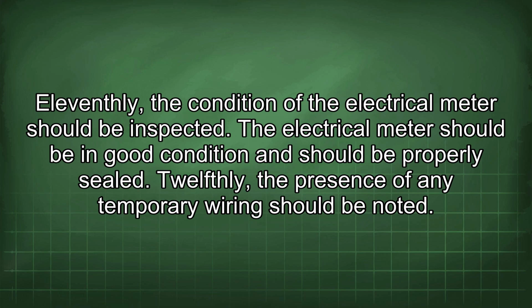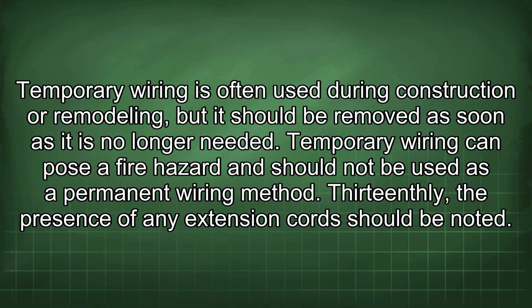12thly, the presence of any temporary wiring should be noted. Temporary wiring is often used during construction or remodeling, but it should be removed as soon as it is no longer needed. Temporary wiring can pose a fire hazard and should not be used as a permanent wiring method.